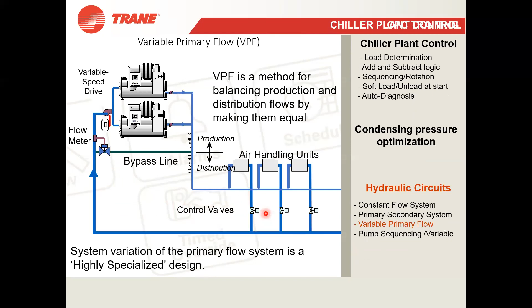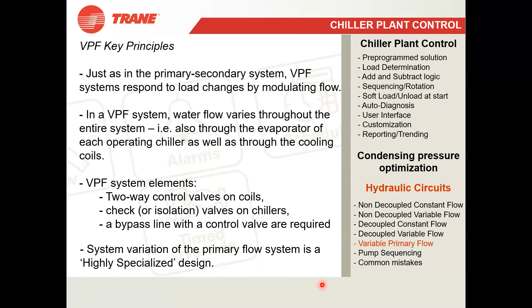Then check or isolation valves on the chillers. A bypass line with a control valve is required. And as I said, this is a very critical and highly specialized system. It is very difficult to control manually. So the CPC will be a great help to control this kind of complex system. Now, pump sequencing, I have told you, and frequency variation also can be done using this chiller plant control.